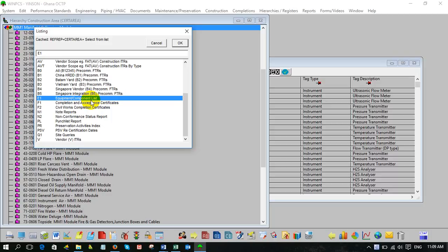See, run preservation schedule. But why so many? Sometimes week 44, because you cannot start preservation all together at one time. If I put 150 equipment together one time, 4 weeks later another 150, then how do you divide your time? So you need to split, you need to be smart. For example, now I got 30 items coming at one time. You split the 30 items into 10, 10, 10. I start 10 this week, 10 next week, 10 the other week. So 4 weeks later 10, 4 weeks later 10. So every week I got preservation.